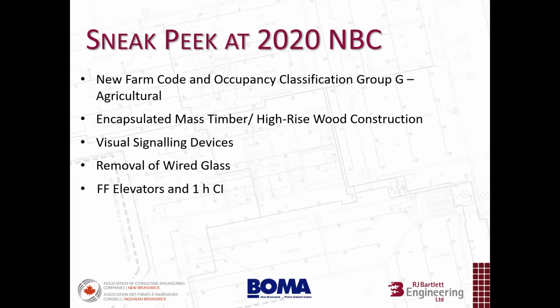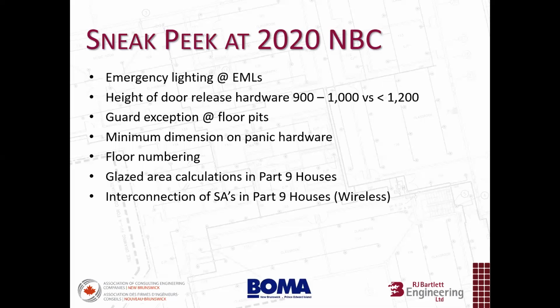Some circuit integrity requirements for conductors serving firefighter elevators are going to be in the 2020. There's emergency lighting at magnetic locks; right now it's just noted in Section 3.4.6.16 of the code. So where we went over and identified that this emergency lighting is a good thing to have by these doors, it's now going to be actually in the emergency lighting section of the code as well. That's a small, minor change, but these types of improvements help us all navigate the code and not miss these sorts of things. The height of the door release hardware is going to be reduced to between 900 and 1,000 millimeters from the floor, versus what it was before, being less than 1,200.